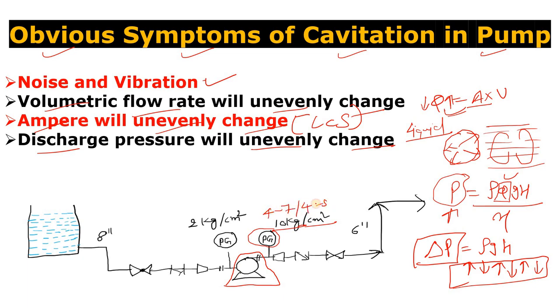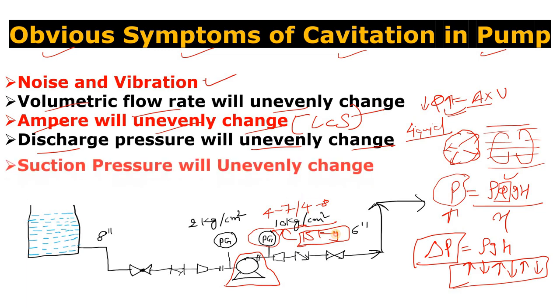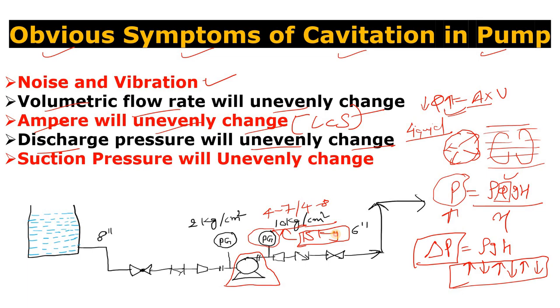During cavitation, if the normal pressure is 10 kg per centimeter square, it may fluctuate to around 4 to 7 or 4 to 8. Please let me know in the comments what you think if the discharge pressure shows 12 to 15 kg — would that also be cavitation or some other reason? The last symptom is that the suction pressure will also unevenly change. As vapor bubbles form, the pressure at the eye of the pump will increase and decrease, impacting the suction side pressure as well.